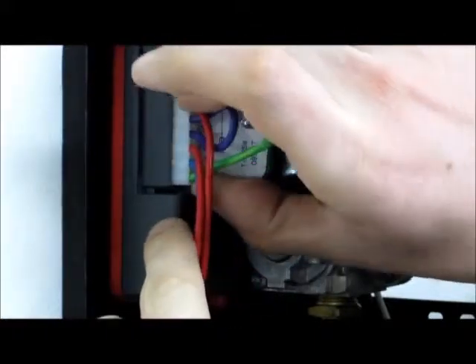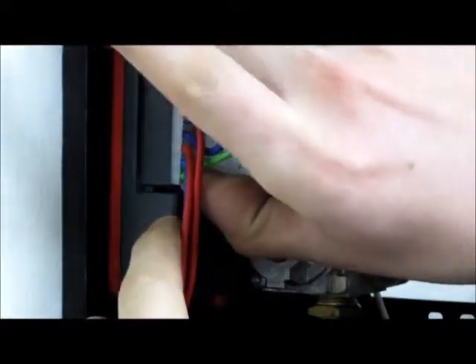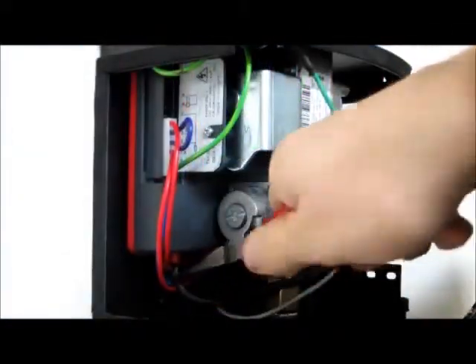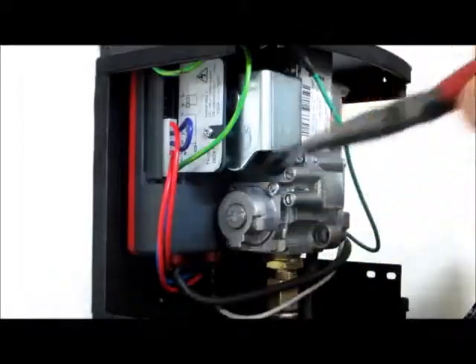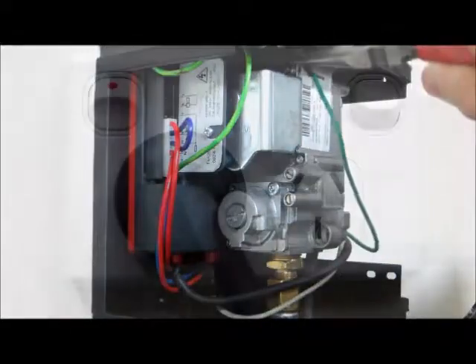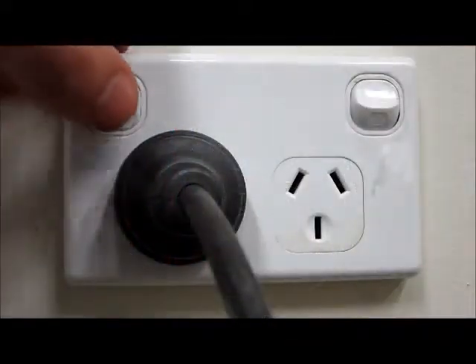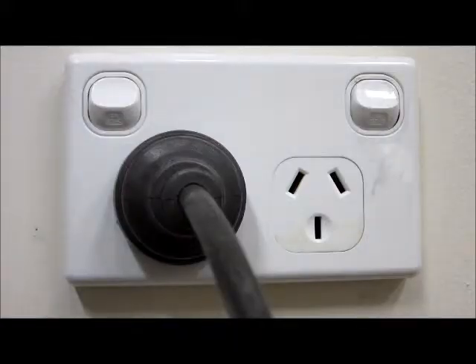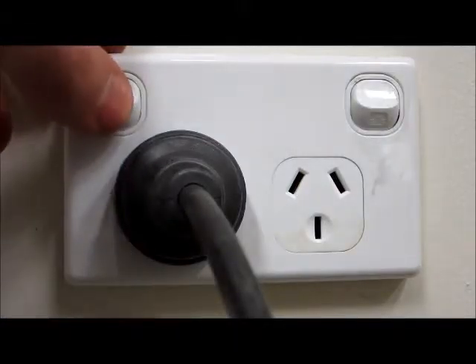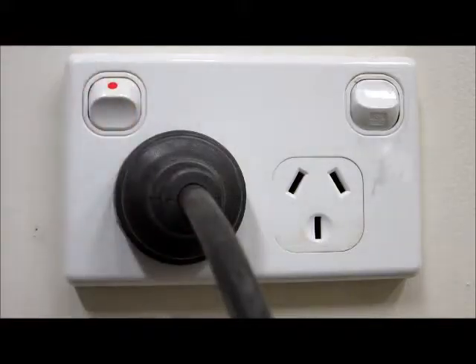The green earth wire must be at the very bottom as indicated. Check that the ignition and earth terminals are firmly secured into their positions. Turn the gas supply off and check that power is running to the heater by turning the heater off for 30 seconds to ensure that the unit is no longer in lockout mode from any previous failed attempts.